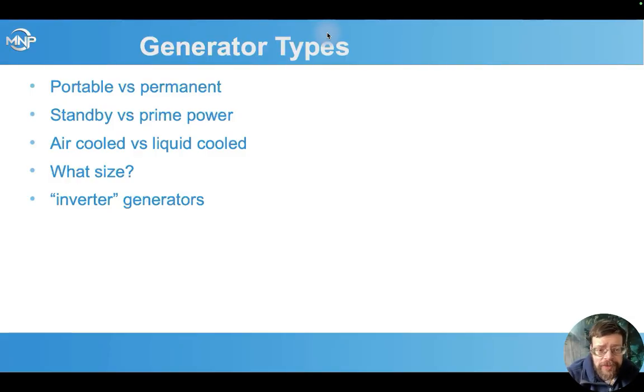Looking at air-cooled versus liquid-cooled, generally most of our standby ones are going to be air-cooled nowadays, and often those are 1,500 to maybe 2,500 hour expected runtime before they're worn out. Liquid-cooled ones usually run at 1,800 RPMs instead of 3,600 and have much longer design lifespans, often 10,000 hours between rebuilds or replacements. In the sub 20 kilowatt size, it's a lot harder to find the liquid-cooled long life ones, but there are still some options there.